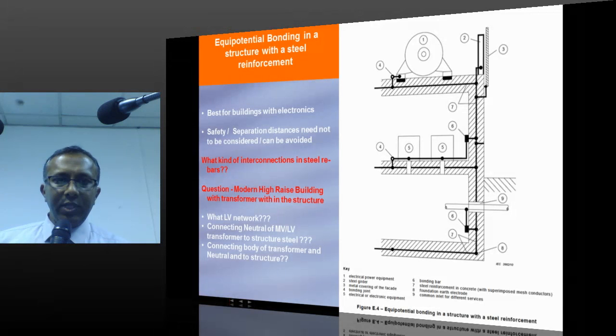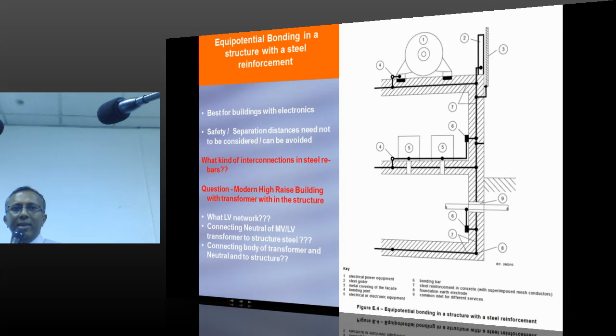I hope you understood. So basically, for a building without insulation against water, that means a plastic sheet, you can use this particular method. That means the foundation ring itself will do, the foundation earthing electrode will do the job. This picture is also from the standard, equipotential bonding within the structure, the previous picture, but in a better way. You see here, you have an antenna which is connected to the structural steel in the slab.